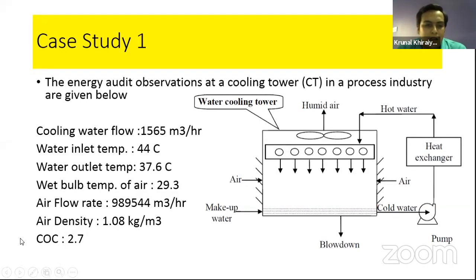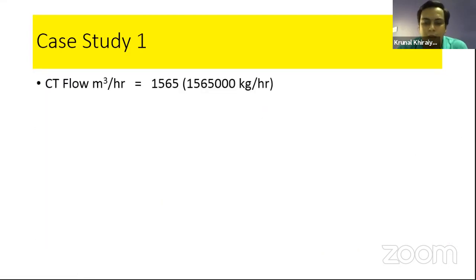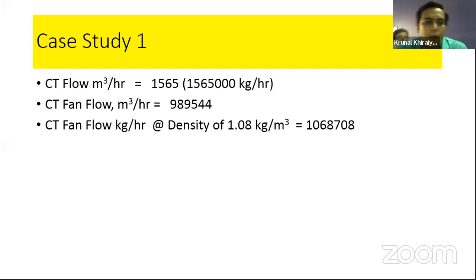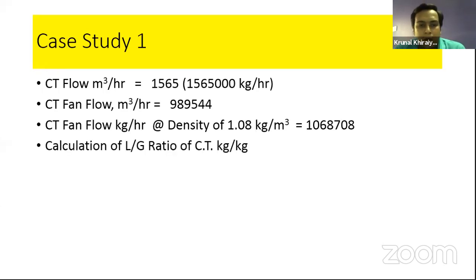And the COC, meaning cycle of concentration, is given as a standard from the manufacturer, and the process operation staff looking after the cooling utilities have maintained a COC of 2.7. So now one by one we are going to calculate the different performance parameters, and from these we can conclude with some comments. Yes, the CT flow rate is given as 1565 meter cube per hour. If you multiply it by 10 to the power 3, it is 1565000 kg per hour. Cooling tower fan flow rate is given as 989544 meter cube per hour. Density of air is given as 1.08. So finally it comes to 1068708 kg per hour.